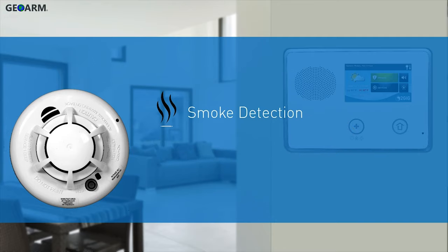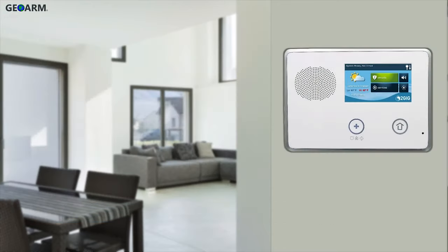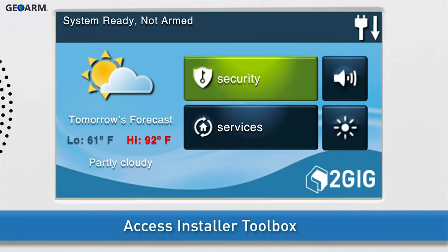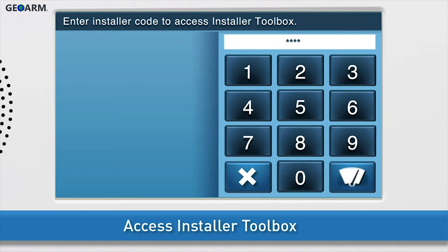To program the Smoke Detection feature into a security zone, you will first need to access the Installer Toolbox. Press the 2GIG logo on your GC2 panel screen, then enter the installer code. The default installer code for the GC2 is 1561.